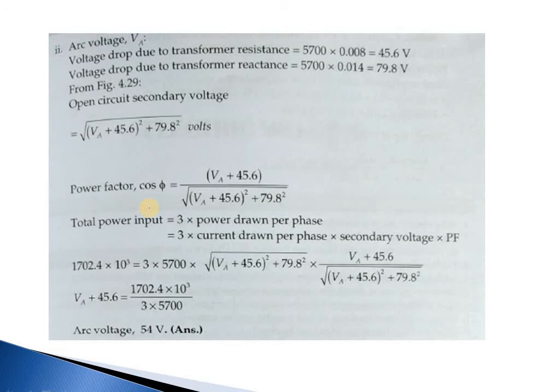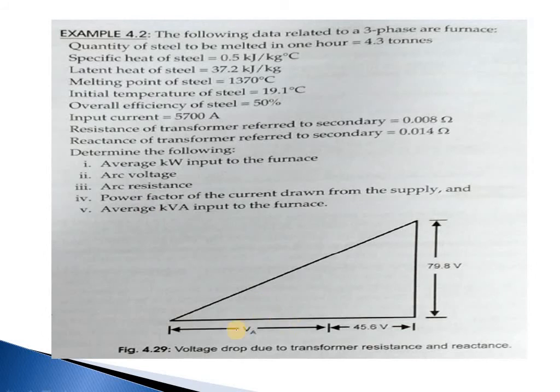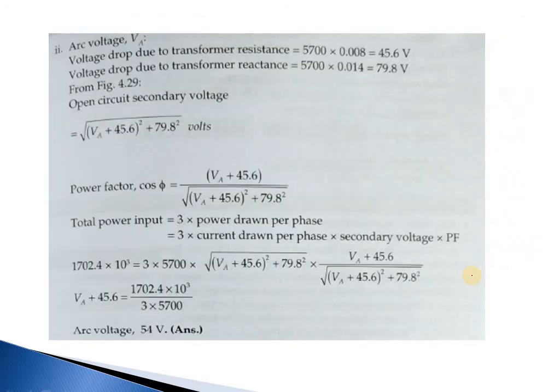Now arc voltage. Voltage drop due to transformer resistance, that is 5,700 into 0.008, that is 45.6. Next, voltage drop due to transformer reactance, that is 5,700 into 0.014, that is 79.8. Now open circuit secondary voltage from the figure we can calculate: it is the square root of (VA plus 45.6) whole square plus 79.8 square. So we are getting that. This is the open circuit secondary voltage.